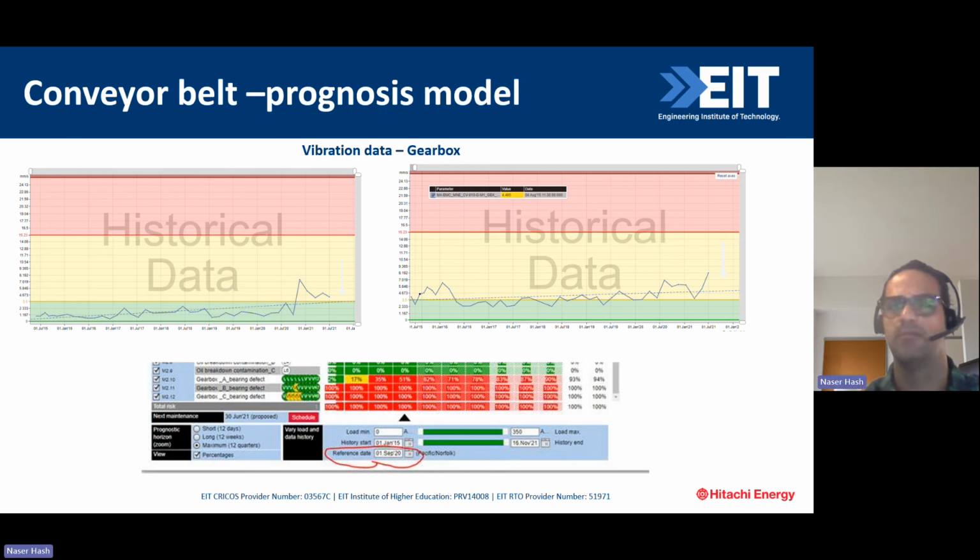And also the turbine, the gearbox side as well. Again, this is another component we can analyze. For example, for that turbine, you could see that the data has changed and moved to the dangerous zone. I don't want to say it's a very dangerous zone, but you can see there is a trend that the Markov chain has calculated for the future, and there would be an increase because the history shows that the temperature or vibration has been at a high level for a long period of time.